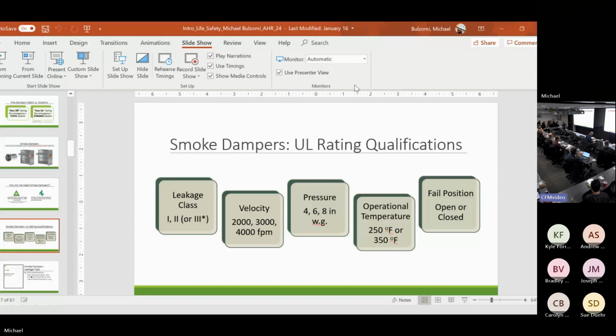If you do not have high velocity ductwork on your job and you specify a damper with a closure velocity other than 2,000 feet per minute, you're not increasing the safety of your building. If your duct spec is all 1,500 feet per minute at 2 inches, and I put a damper that's rated to 4,000 feet at 8 inches, all I did was cost your customer money. The damper is no safer than it was before. It's never going to see that velocity and pressure.